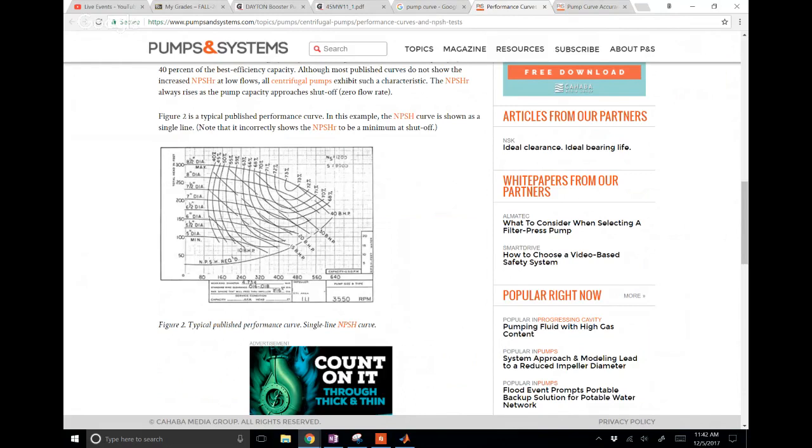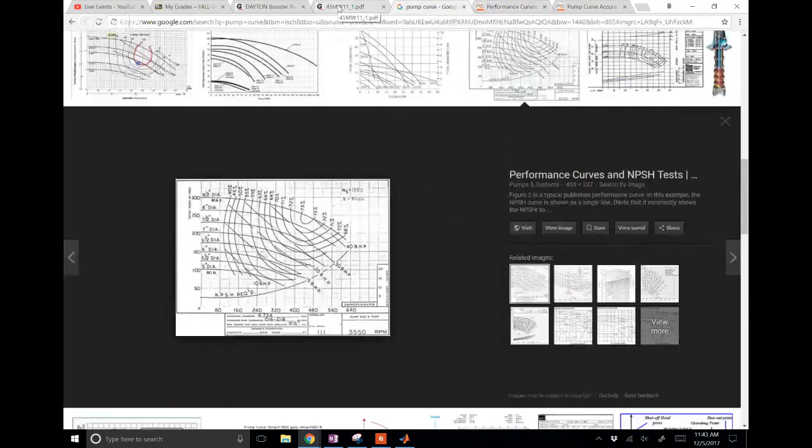Run the calculation, figure out if you want to buy it. And for that matter, this one has, how many diameters? It's got 5.5. It's got a whole bunch of diameters. So I would go down here and pick off the curves all down in here. Just draw lines with the constants for each one of these. Take the supply head back here, and that gives you enough to calculate and go up and down the chart and figure out which one of these you want to buy. And of course, price goes up as you go up the curve.